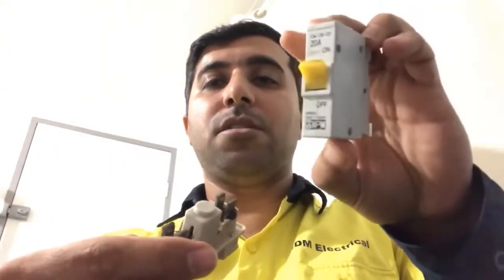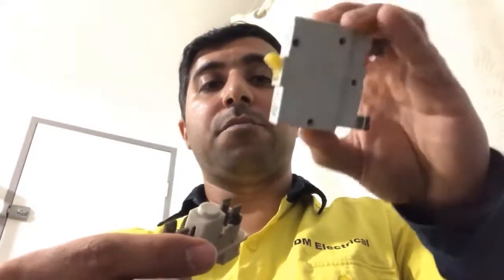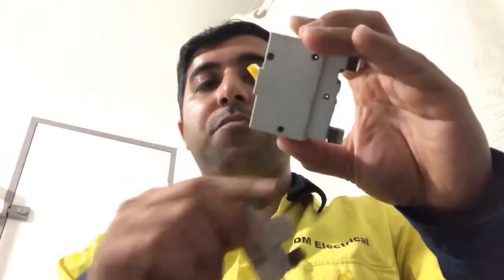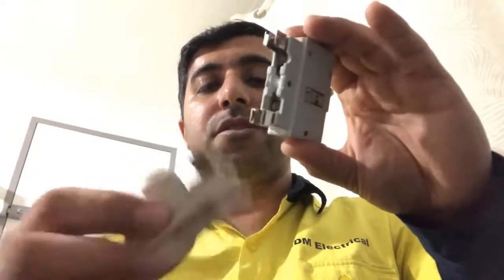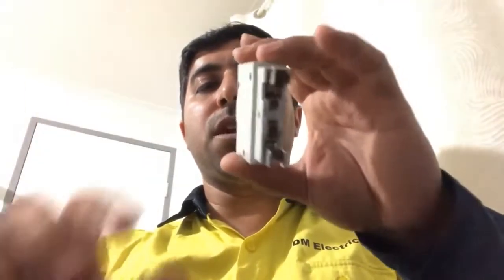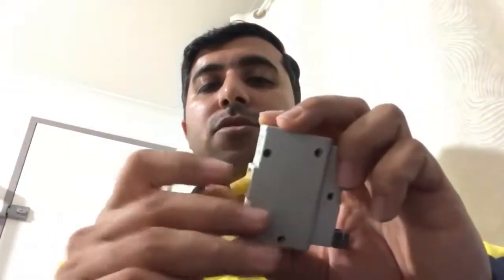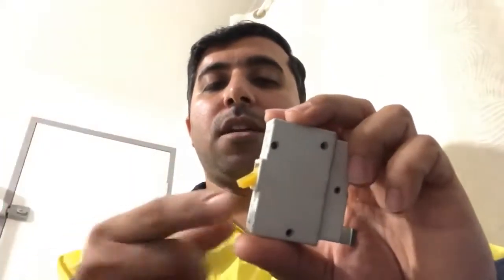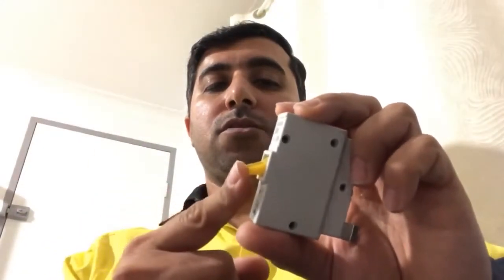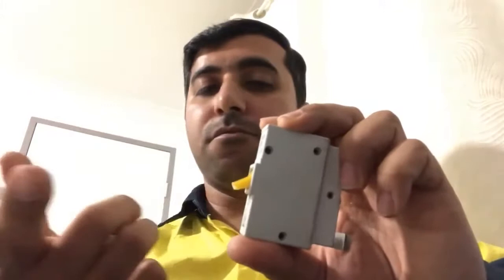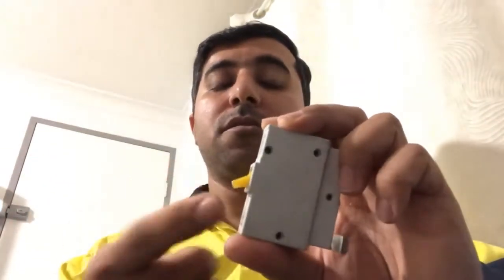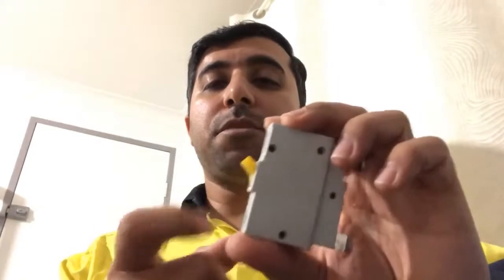The next one is that after that one, something like this came to the market. It's something that you can still find at Bunnings perhaps. That's a circuit breaker with the fitting of the fuse. So you don't actually need to replace the base one. All you need to do is take this one and replace it with that one. It gives you the chance to not rewire it like this one. And whenever there is a fault in the circuit, it's going to trip the circuit. It's an indication for you that there is a fault. When the fault has been removed, you can trip it back on.